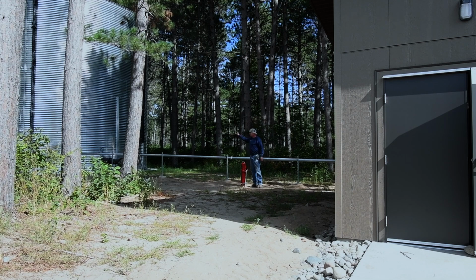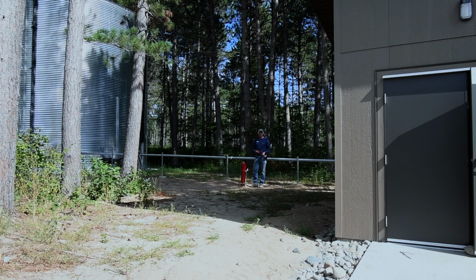This is a shut off between the tank and the pump house. So if you shut this valve, again, you just lift the handle up, put the wrench on the top, turn it to the right. As soon as it gets turned, the panel's going to pick it up. But again, remember, anytime you work on any sprinkler, you have to get a hold of Ben. That's the most important thing, because otherwise, if you turn the valve, it's going to call into the monitoring company. They're going to have the fire department on the way.